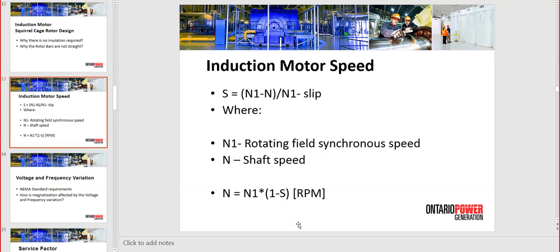This one is the slip, right? So what is the slip? It is the difference between the speed of the rotating field minus the speed of the shaft, and for a relative percentage you divide by the rotating field speed. So like we said, 1800 minus 1750 over 1800, and then multiply by 100, and we will have it in percentage. That's usually a certain value on the nameplate.